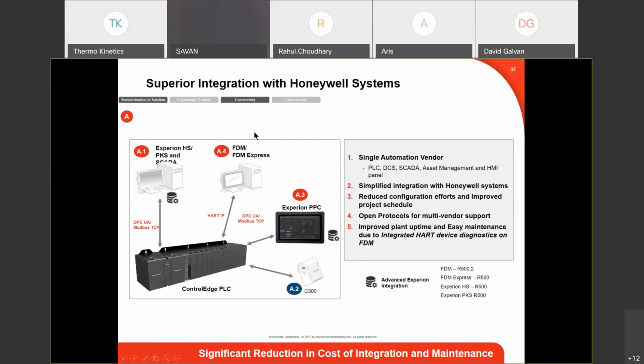And then another thing that we added, because we have the HART card, is that on the configuration side we have the ability to use the 48 HART command function block. So if I want to use the secondary variable, and I want to strip that HART data off of that device and actually use those variables for control, I can do that. I can assign those variables in that logic block utilizing that 48 command block, and I'll show you that later in the presentation. Really, really cool stuff.